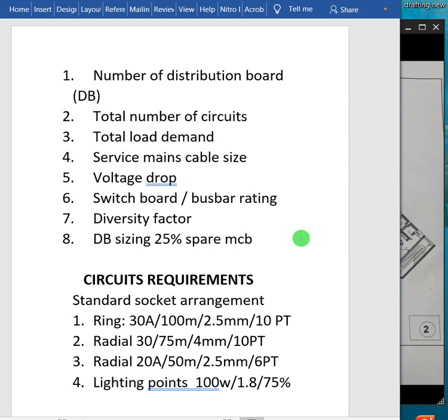Any lighting system that uses chokes and igniters and capacitors falls into the factor of 1.8 in order to augment the starting current of this lighting system, and to augment the power losses from the switching systems. So we're going to add this to give allowance for what I've just explained.